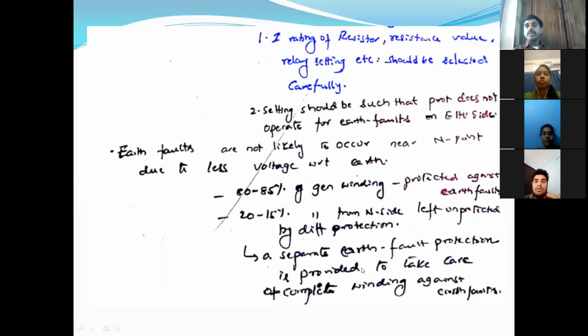The current rating of the resistor, resistance value, relay setting, etc. should be selected carefully. That's what we discussed in the previous slide, these two points. Earth faults are not likely to occur near the neutral point due to less voltage with respect to earth. That's what I have shown in the previous slide. So as I said repeatedly, 80 to 85% of the winding is protected against earth faults. 20 to 15% is left unprotected. A separate earth fault protection should be provided to take care of the complete winding against earth fault.